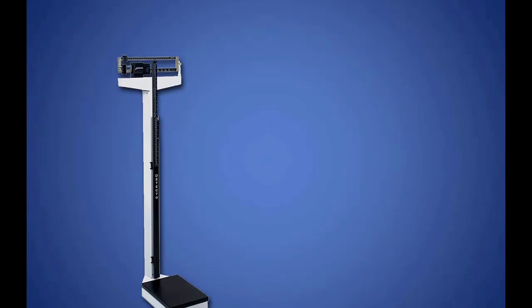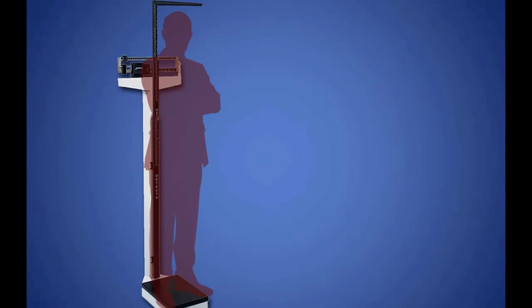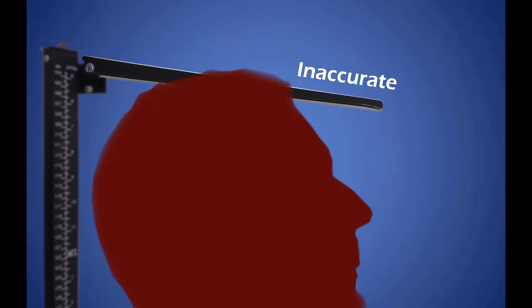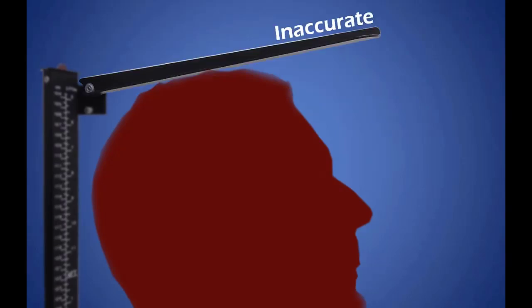Here's a general overview of how the height rod works. The patient steps on the platform. Raise the height rod so the headpiece is above the patient's head. Lower the headpiece onto the patient's head. Make sure the headpiece is flat. If it is slanted downward or upward, you will produce an inaccurate result. Remember, make sure the headpiece lays flat atop the patient's head.